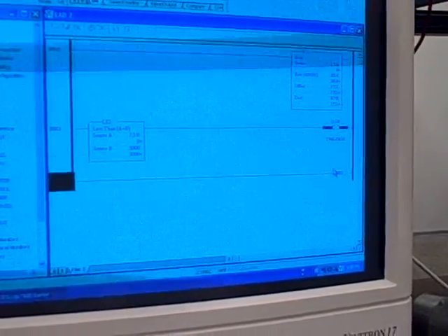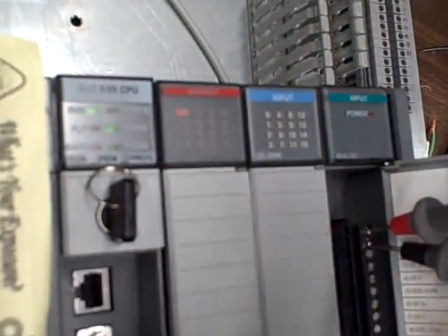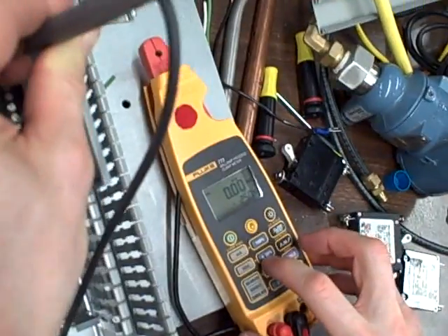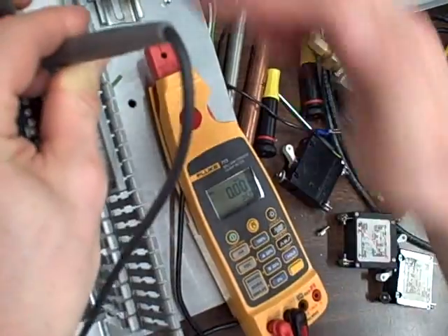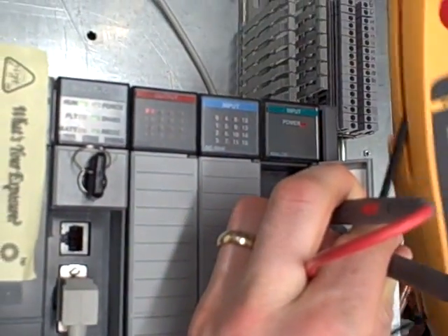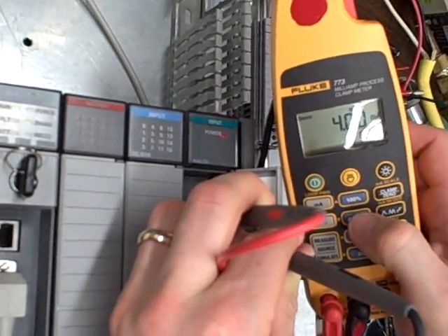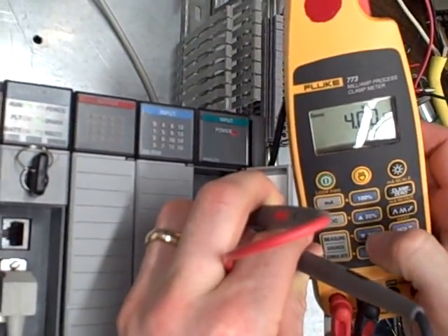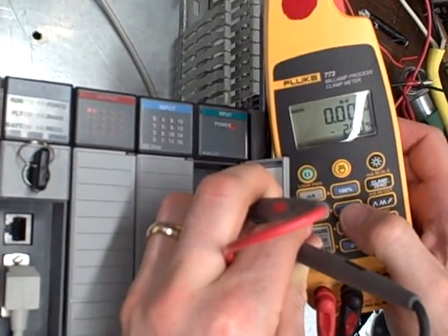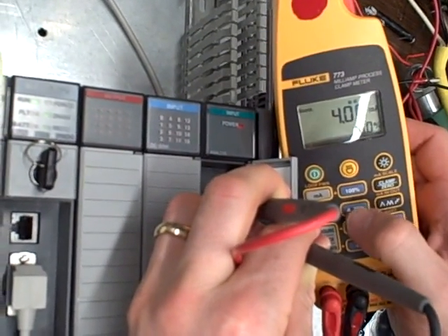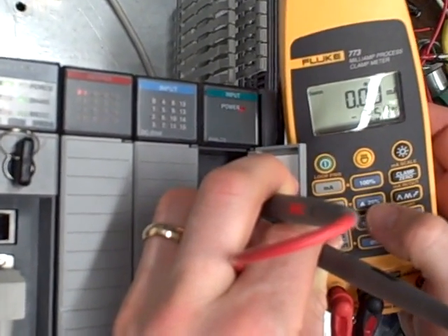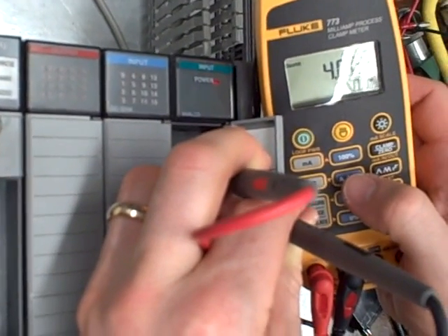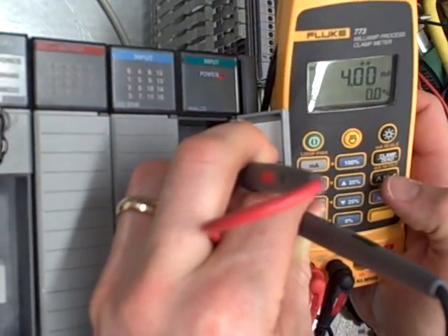Move the camera over here for a moment if you could. And we can see the output. There's the output channel, it's lit. It's actually lighting that output up. As I make the milliamps go up, notice that light is going to go off. So here we go, turning the milliamps up and the light goes off. The milliamps go down, light comes on. So I've got the automatic detection of a milliamp problem, being too far below 4 milliamps.